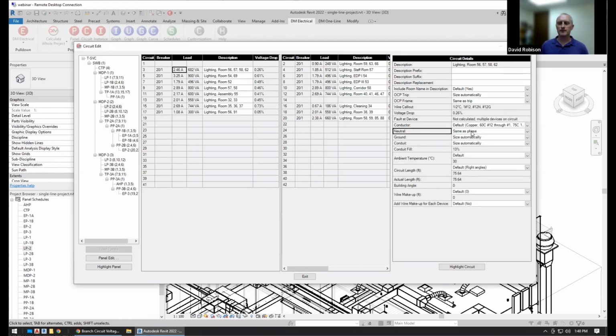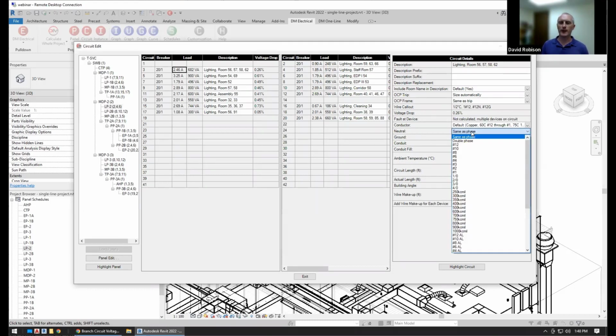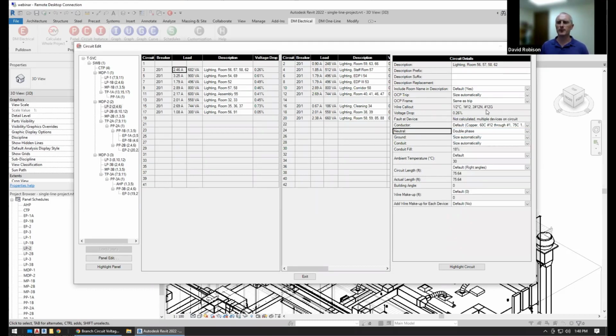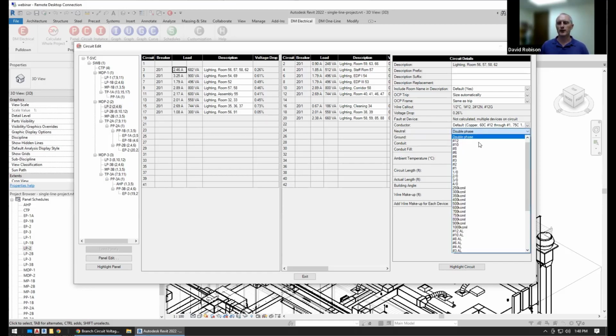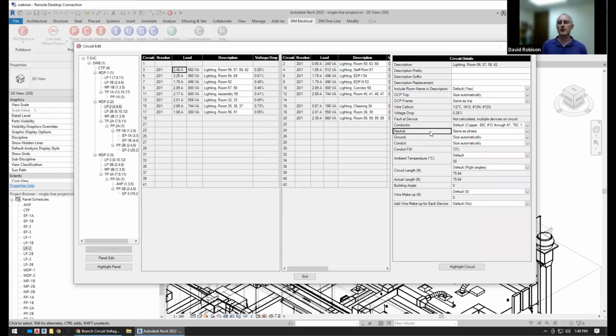For neutral, we have the option to match the phase wire. We can do double phase, and when we do that, we actually put in two wires for the neutral. Or you can specify a specific neutral wire. On three-phase circuits, if you double the neutral, the assumption built into the software is that it's usually because you actually have a current ending up on that neutral. So that's why you're upsizing it. And if you do have a current on a doubled neutral, you end up with 5 current carrying conductors instead of 4 if you have a 3-phase circuit.